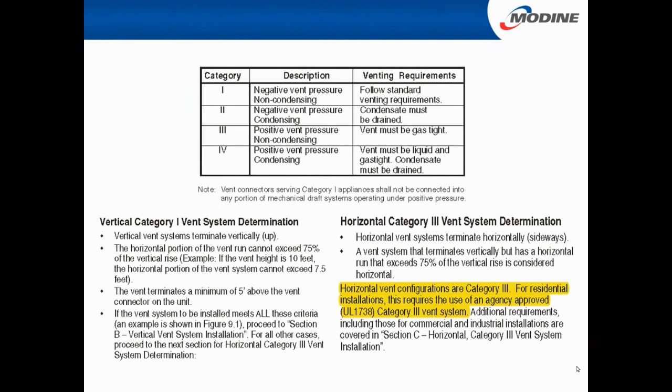That was the first time I ever ran into it. A lot of times we'll just get a call and they'll call out a hot dog or, occasionally, a PDP, but most of the time that's all I really run into. You want to run at least 1 foot of straight pipe before your 90. A lot of people will hang it, and there's not enough space to put that 1 foot piece on. All you can do is give them the recommendation, or just fail it. You should come out 1 foot before you make the turn.